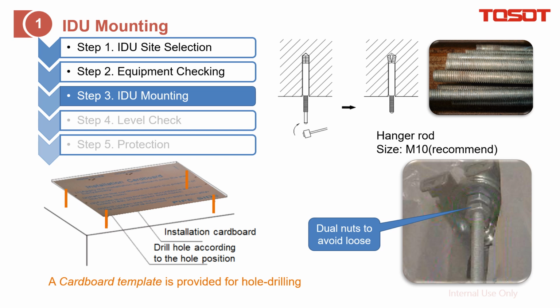And the next is to install the indoor unit. Before that, you need to drill holes in the ceiling. We already provide you a cardboard template for your reference to drill the holes. You just put the cardboard on, and at this position you can drill a hole. After you drill the hole, you need to install the hanger rod, and we recommend M10 for installing the indoor unit. And last, at the lower side of the nuts, you need to apply double nuts to avoid loosening.